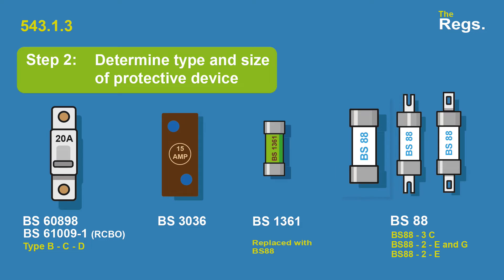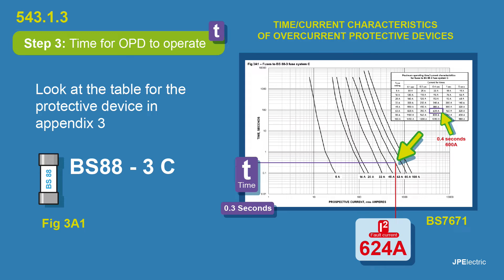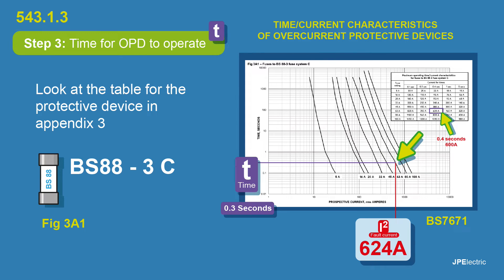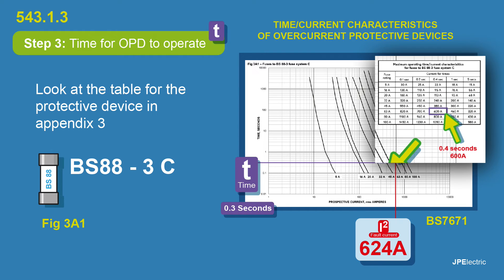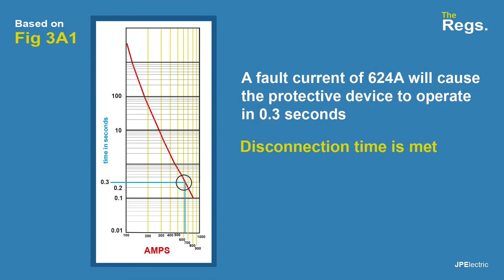We can now look up the disconnection times for this type of device. Step three: the time for the overcurrent protective device to operate. We'll find this in Appendix 3, the time-current characteristics for overcurrent protective devices — figure 3A1, which is fuses to BS88-3. Following along the bottom line for prospective current in amps, we're looking for 624. Going up to the diagonal line and across, a fault current of 624 amps will operate the device in 0.3 seconds. The table shows that for 0.4 seconds it would be 600 amps, but since we've got an actual measured fault current of 624 amps, that trips this BS88 fuse in 0.3 seconds.